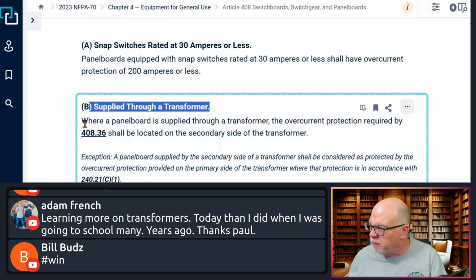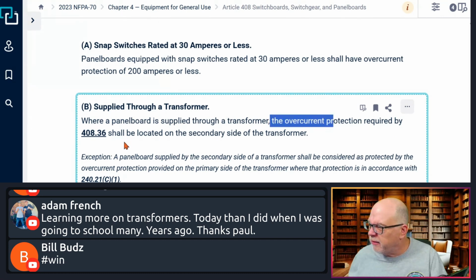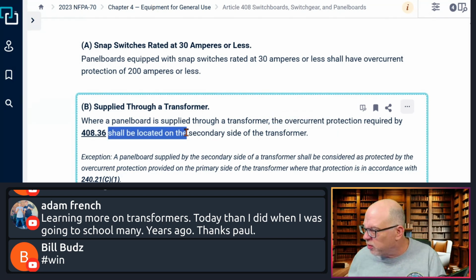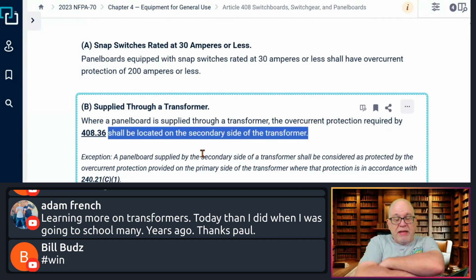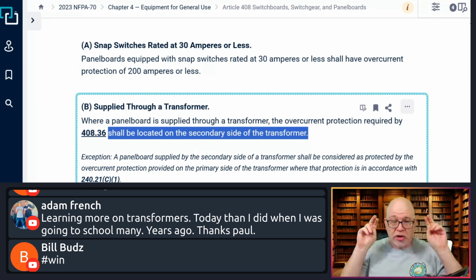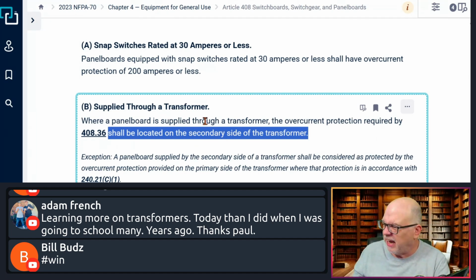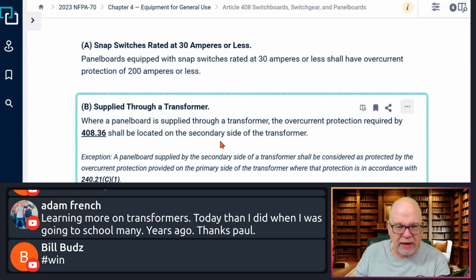Now, here's what it says. It says where a panel board is supplied through a transformer, the overcurrent protection required by 408.36, now read this, shall be located on the secondary side of the transformer. Okay. And so it's either going to be before it gets to the panel, or it could be in the panel, as long as we're following the secondary conductor rules and the lengths, the 10-foot rule, 25-foot rule, secondary conductor rules. The key here is I need to have, where a panel is supplied or powered through a transformer, okay, then I have to have that overcurrent protection required by 408.36.